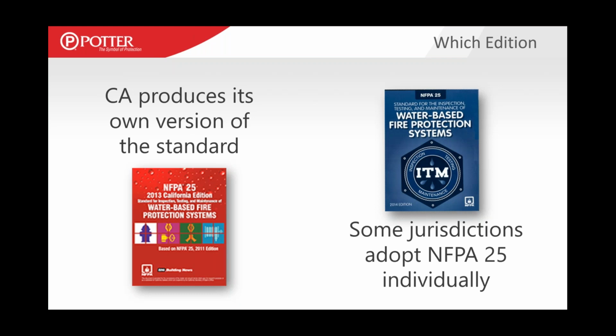Sometimes states can adopt their own NFPA 25. California, for example, produces its own version. It's the California edition of NFPA 25. So regardless of what cycles you may be in the fire code, in some states the NFPA 25 may be a freestanding document. Some jurisdictions adopt NFPA 25 separately. The state of Florida, for example, adopts NFPA 25 not only as a reference in the fire code, but they also adopt it as a freestanding document. It's a freestanding adoption, so that may change mid-cycle. So it's not always tied to the fire code, but it's often tied to the fire code.